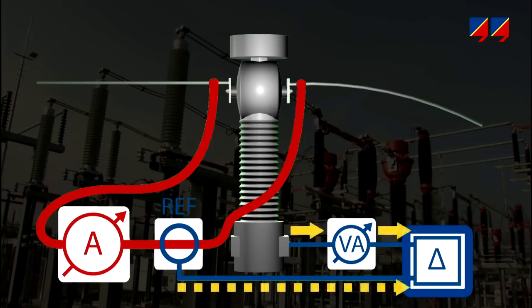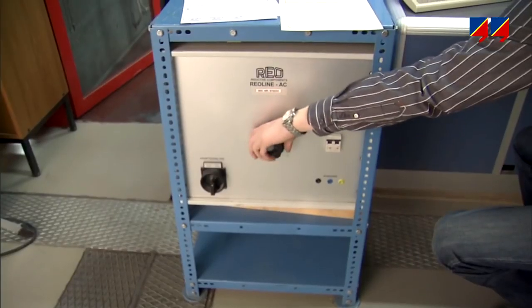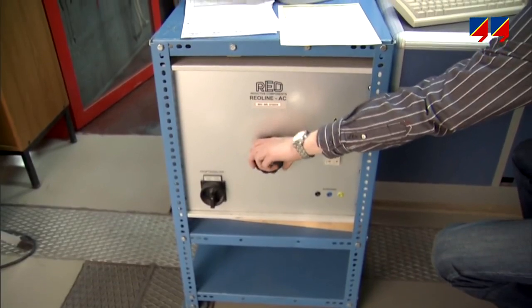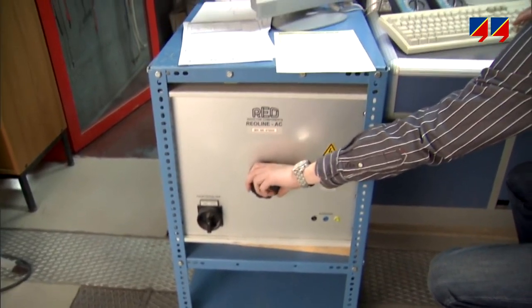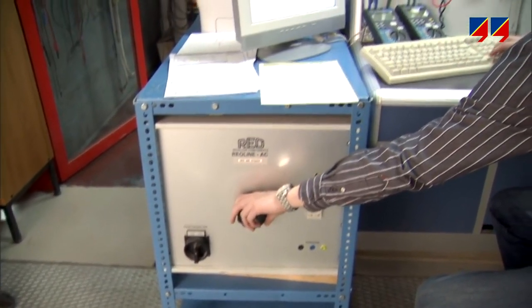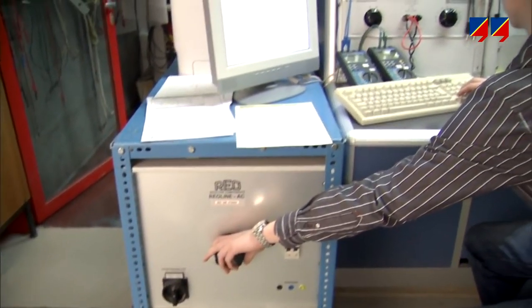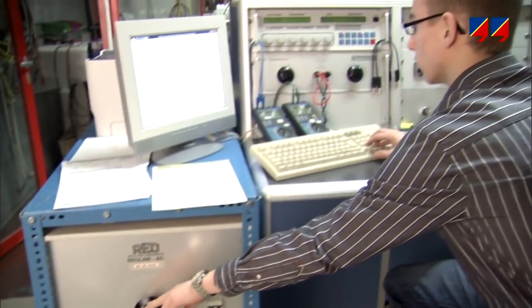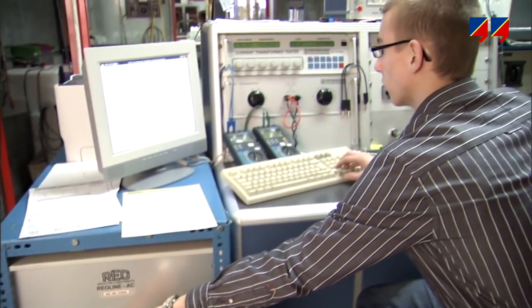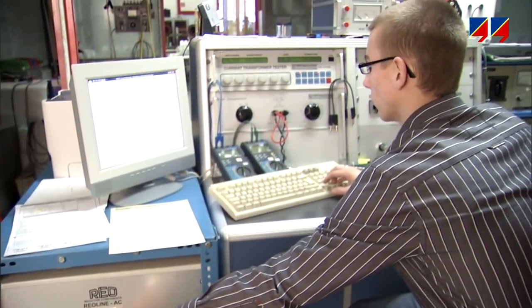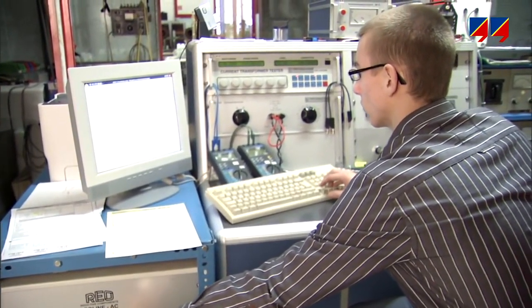Via a measurement bridge, the output currents from both CTs are compared in amplitude and phase. With this method, all current and burden value combinations defined by the relevant international standards can be verified, and the CT's compliance can be assessed.